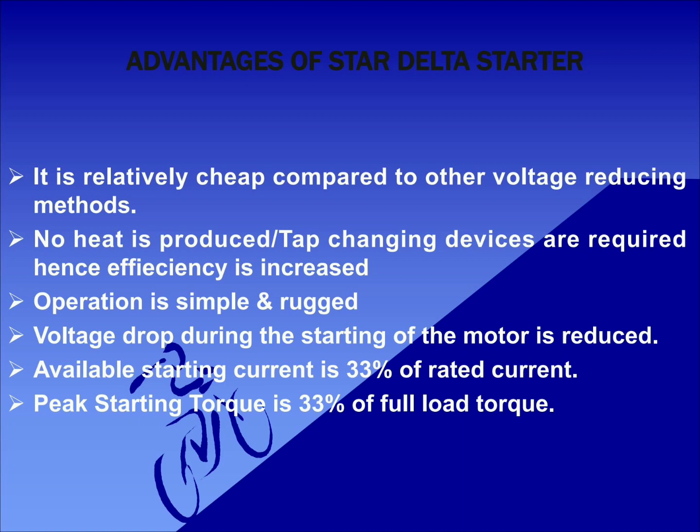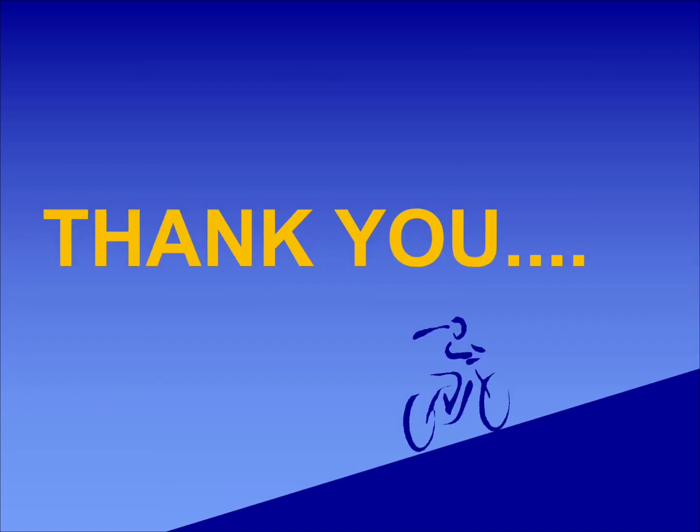Now let's see the advantages of a star-delta starter. It's relatively cheap compared to other methods. No heat is produced and no tap changing devices are used, hence efficiency is increased. Operation is simple and rugged. Voltage drop during the starting of the motor is reduced, and the available current and the torque are reduced to 33% of the full load values. This was all about the star-delta starter.